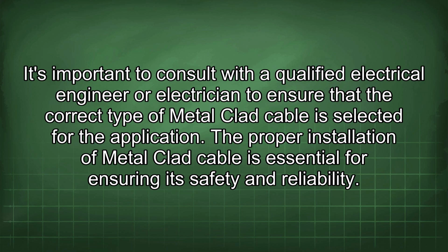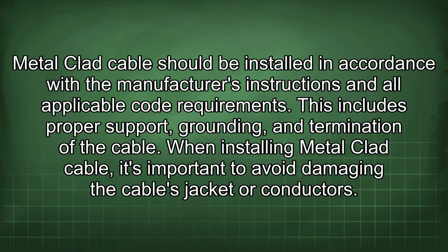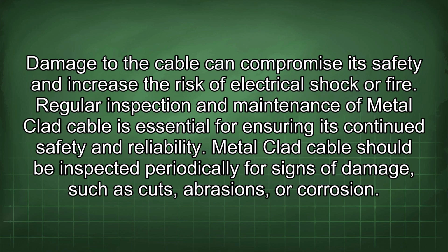The proper installation of metal-clad cable is essential for ensuring its safety and reliability. Metal-clad cable should be installed in accordance with the manufacturer's instructions and all applicable code requirements. This includes proper support, grounding, and termination of the cable. When installing metal-clad cable, it's important to avoid damaging the cable's jacket or conductors. Damage to the cable can compromise its safety and increase the risk of electrical shock or fire.